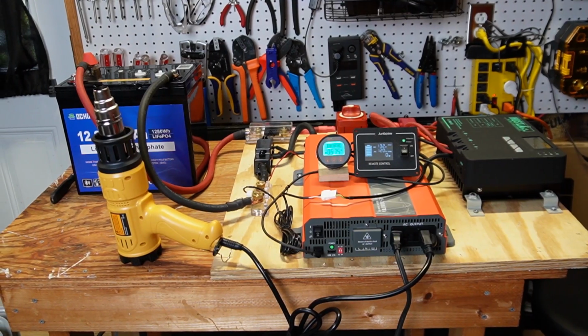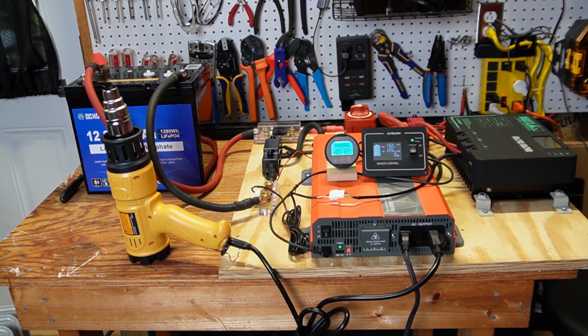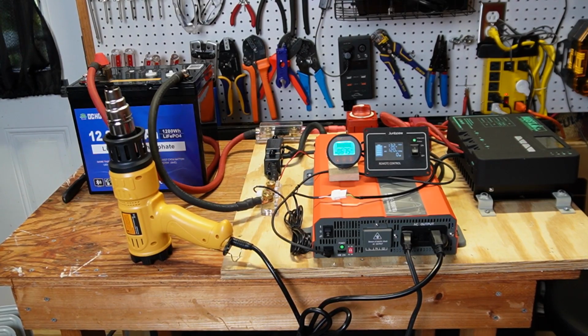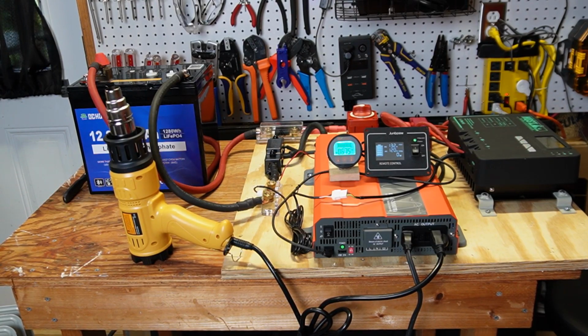Okay, so now we're going to do a max load test. This battery claims a 100 amp continuous discharge, and we're going to put that to the test. I'm going to see if I can discharge it just slightly over 100 amps for 5 minutes, make sure everything looks good. We'll check with a thermal cam to make sure there's no heat buildup on the battery.